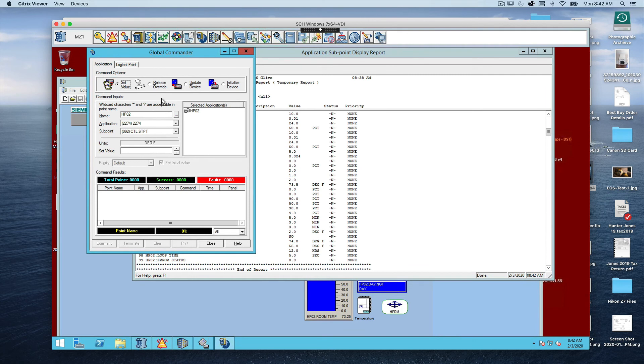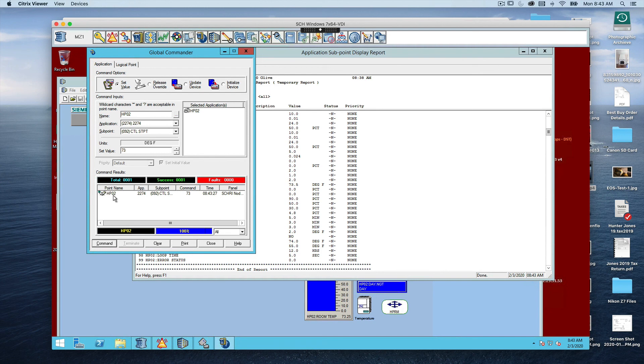A global commander screen opens up. In the global commander you have a choice called Set Value — the set value for that point is currently 74. We're going to click in the box, type in 73, then go down to the Command function and click Command. Watching the command results section, you can see that we just changed the temperature on the heat pump from 74 to 73 degrees. Let's go ahead and close this out.